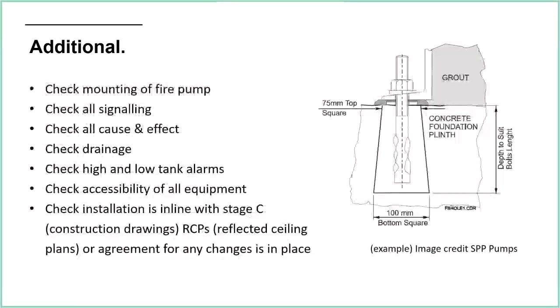All the signalling, so every single thing which is monitored, every single panel that's displaying information, needs to be checked. All cause and effect as well. So the sprinkler system alarms may well feed into other systems, which are then doing other things. So all of that needs to be checked to make sure everything is working.